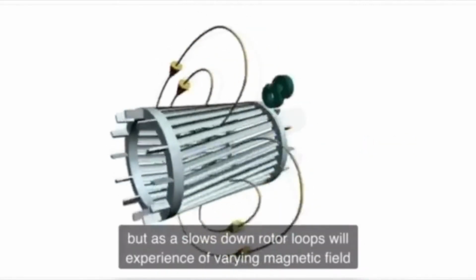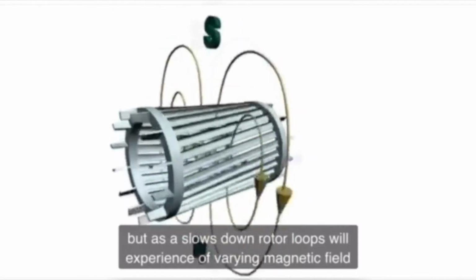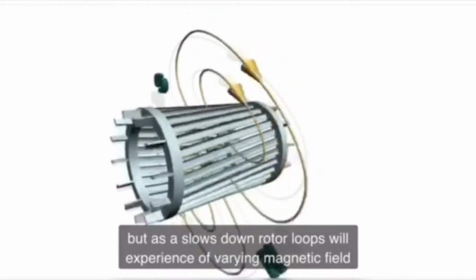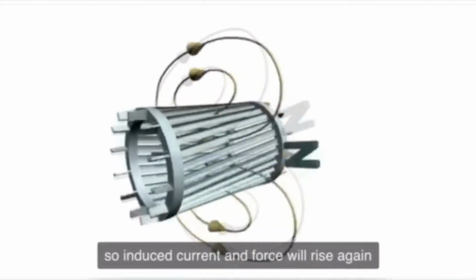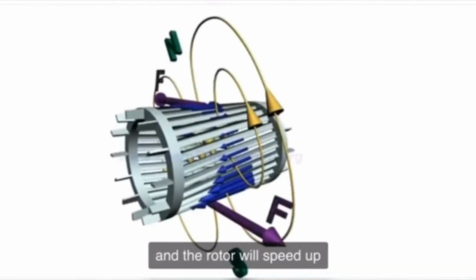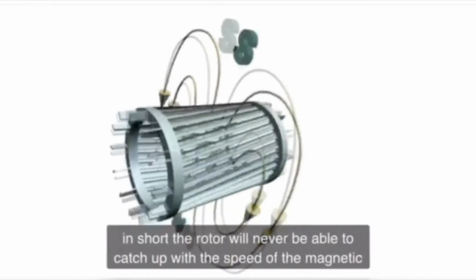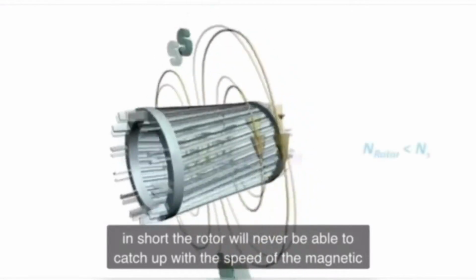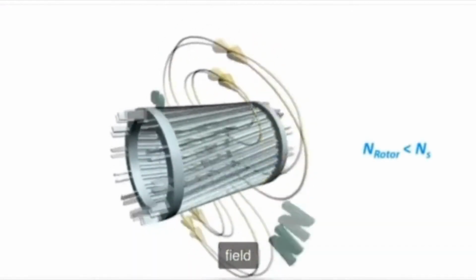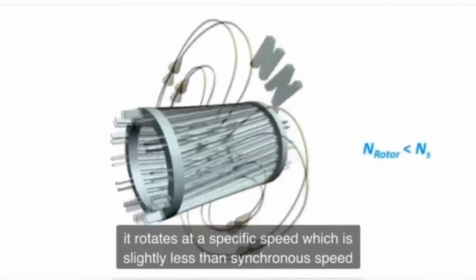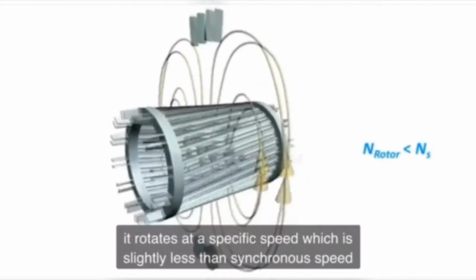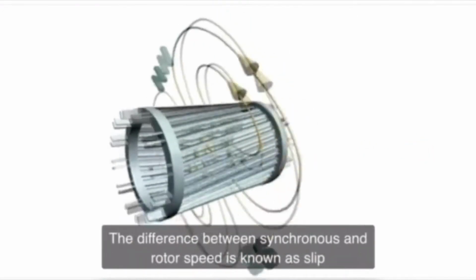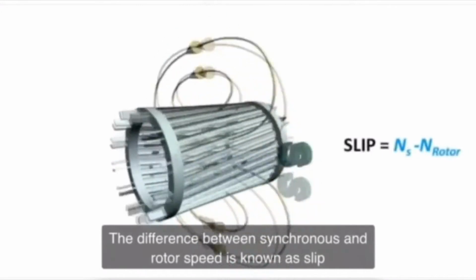But as it slows down, rotor loops will experience a varying magnetic field. So, induced current and force will rise again. And the rotor will speed up. In short, the rotor will never be able to catch up with the speed of the magnetic field. It rotates at a specific speed, which is slightly less than synchronous speed. The difference between synchronous speed and rotor speed is known as slip.